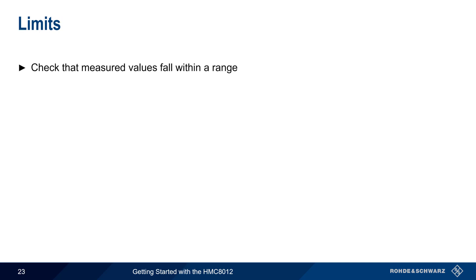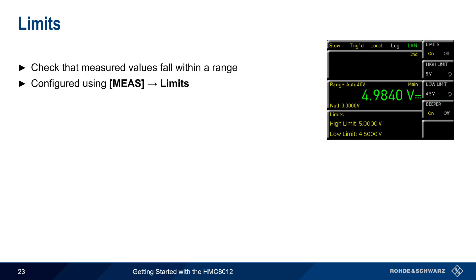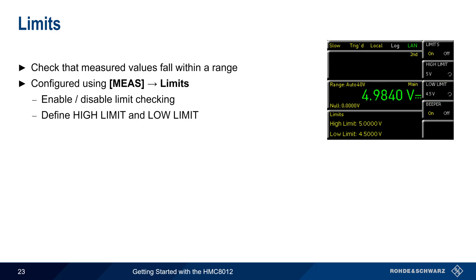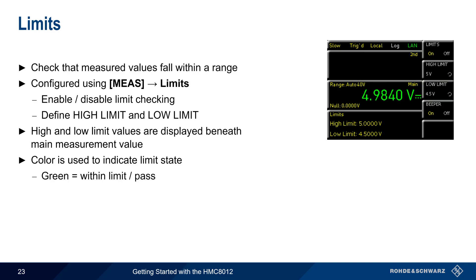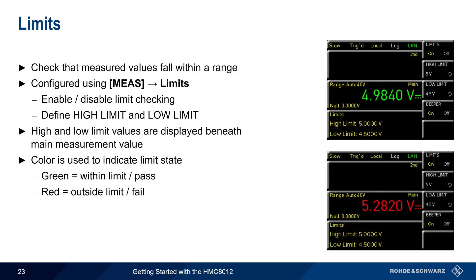Limits are used to check that the measured values fall within a given range, and are configured by pressing the measure hard key and then selecting the soft menu item limits. Here, limit checking is enabled or disabled, and the high and low limit values are defined. Color is used to indicate the limit state: green indicates the measured value is within the limits, and red shows the value is outside the configured limits. An audible tone or beep can also be configured to sound whenever a measurement value falls outside of the limit ranges.